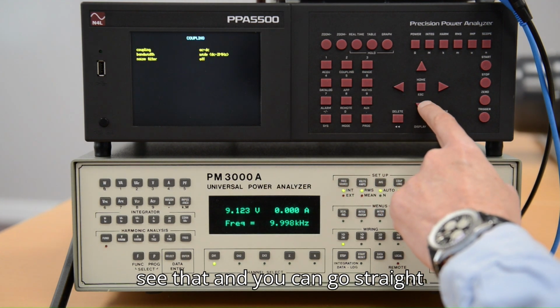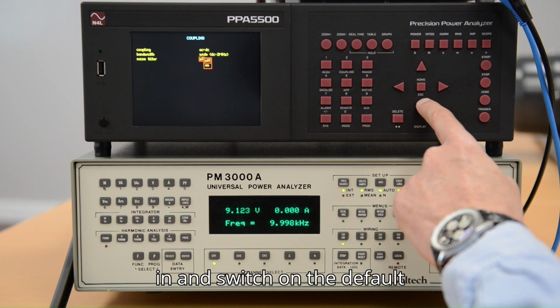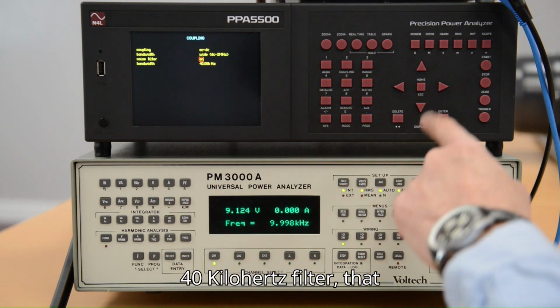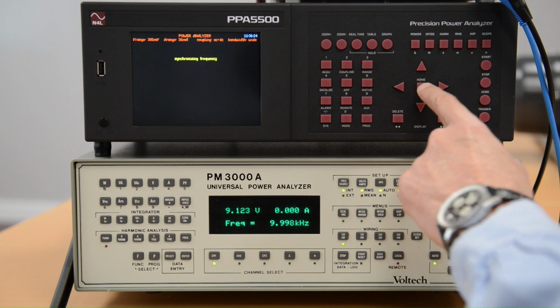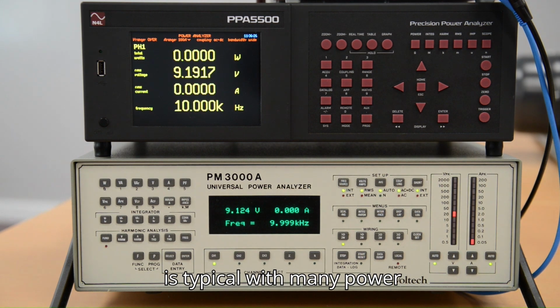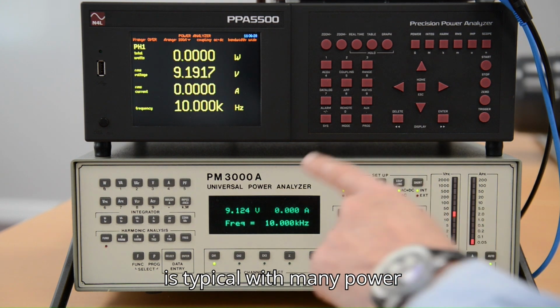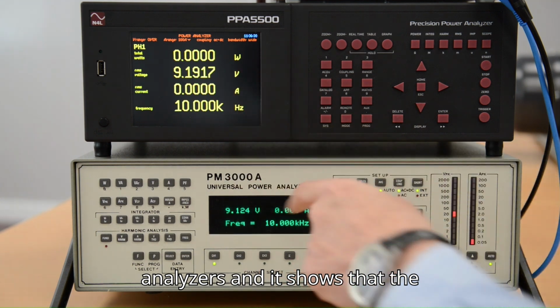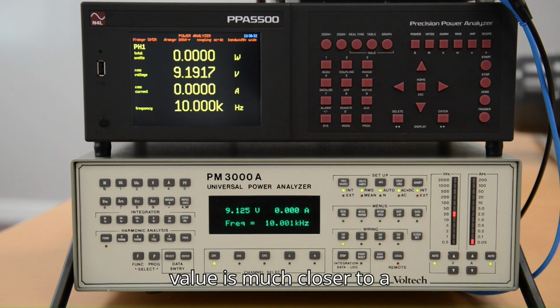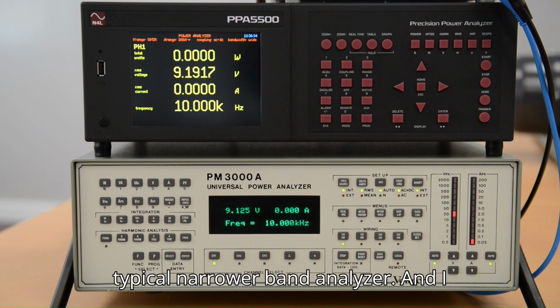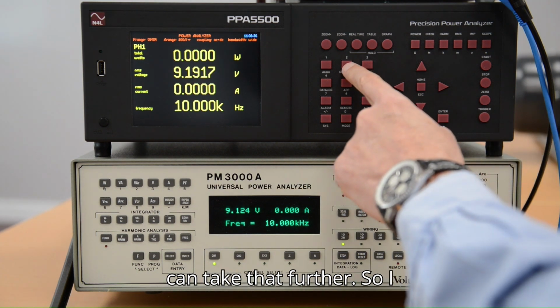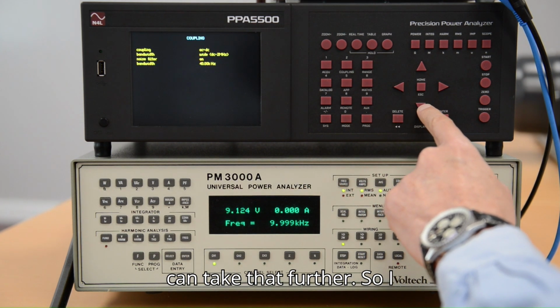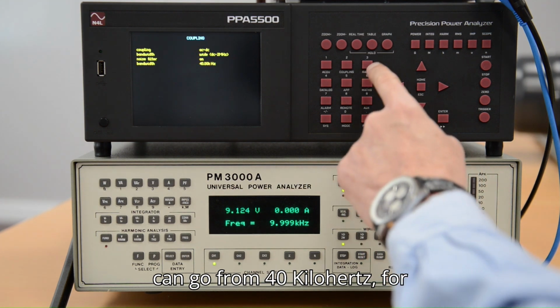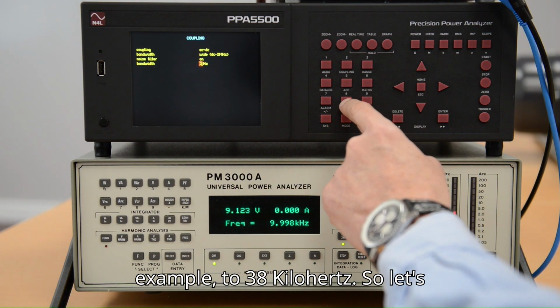And you can go straight in and switch on the default 40 kilohertz filter that is typical with many power analyzers, and it shows that the value is much closer to a typical narrower band analyzer. And I can take that further, so I can go from 40 kilohertz, for example, to 38 kilohertz.